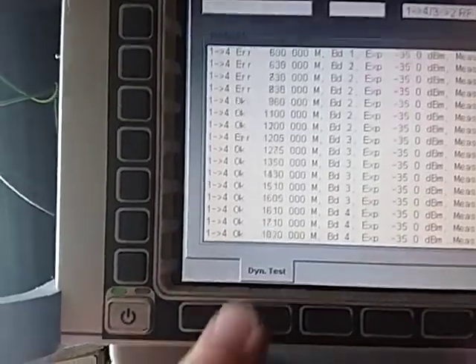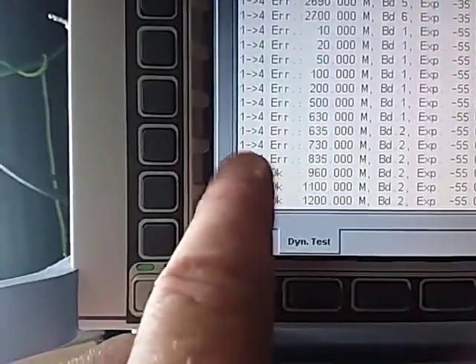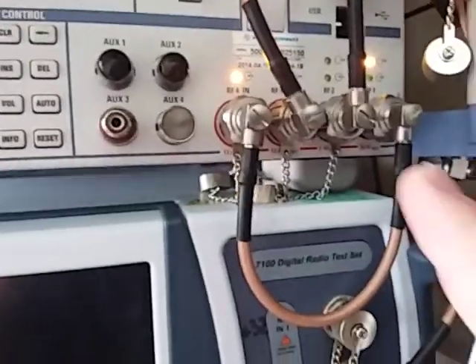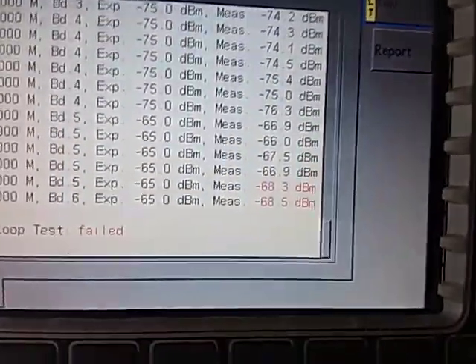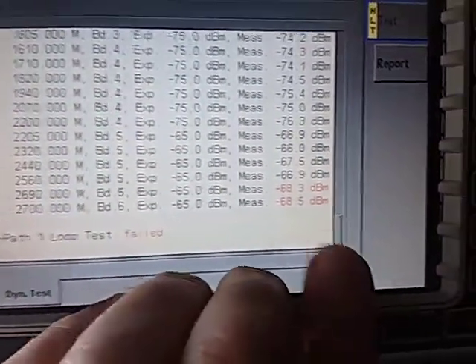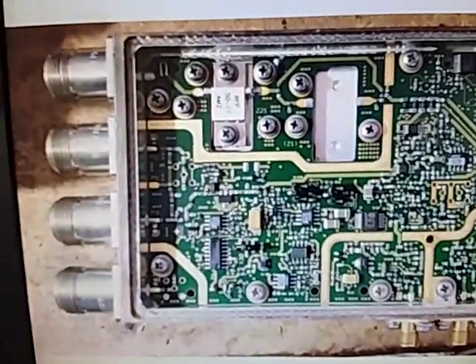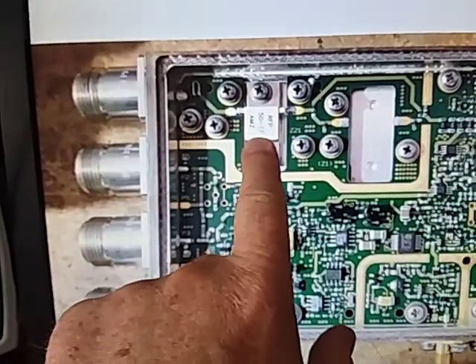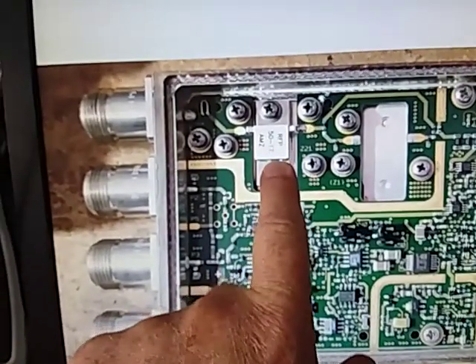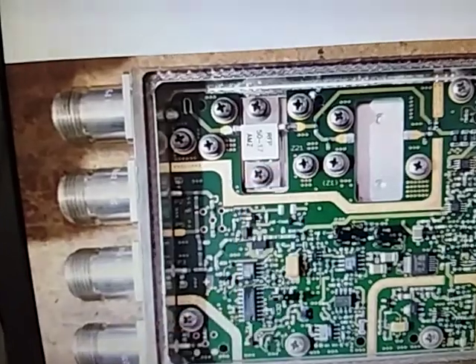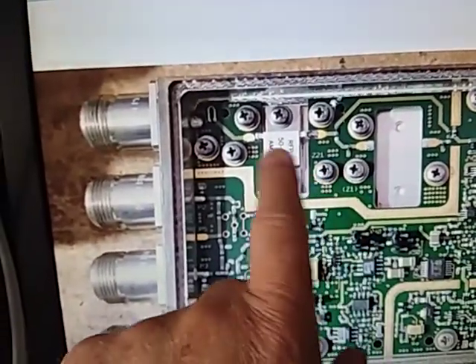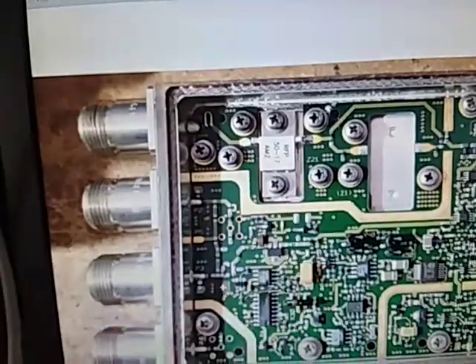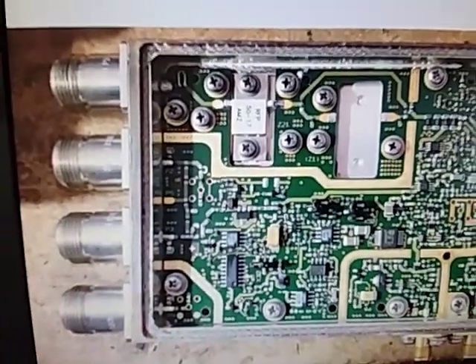We'll select that. To run the test we press the test button and we press go. Now the first thing this is going to do is check loopback one to four, so it's checking at each frequency this path here. And you'll see on my analyzer I fail these tests because it has a problem in the input section. It's possibly that this input one port has been overdriven, which has weakened the attenuator. It could also just be an aging problem.